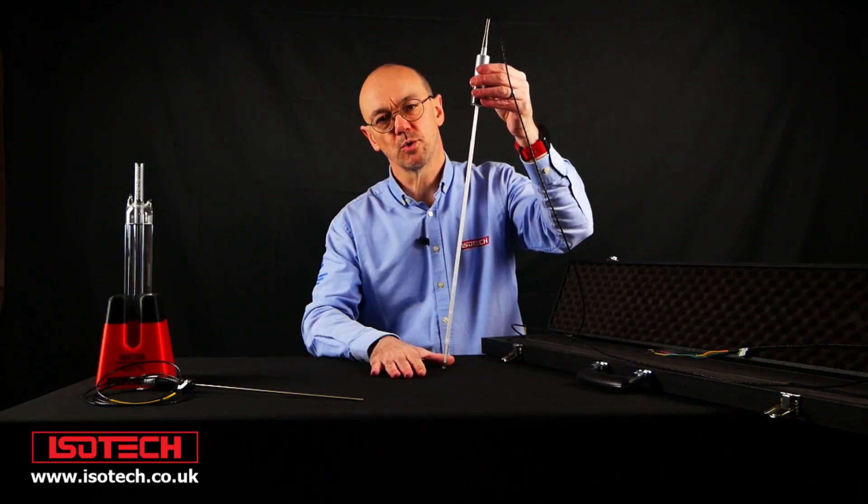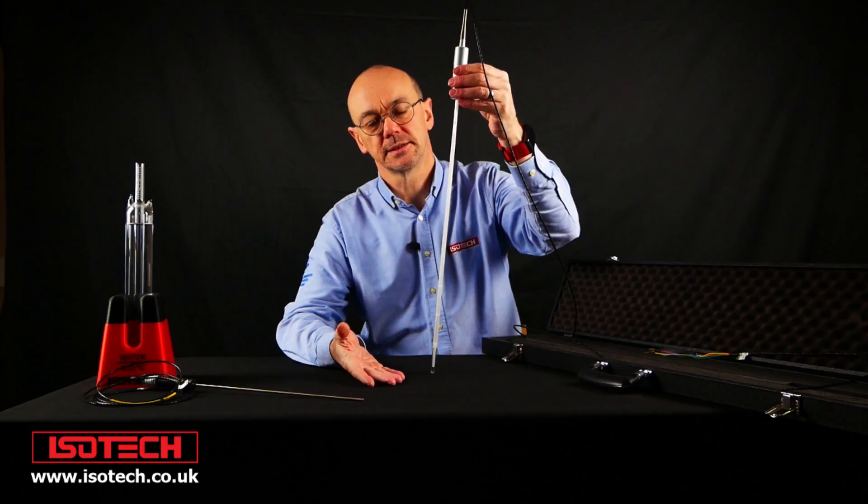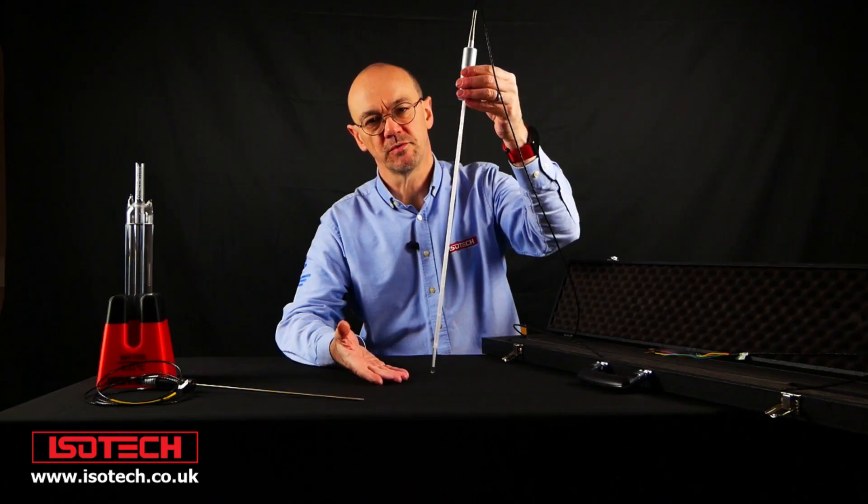We always recommend quartz SPRTs at Isotech. With an SPRT like this, we can't simply obtain a thermometer with calibration and expect to use it for a year with no checks in between.